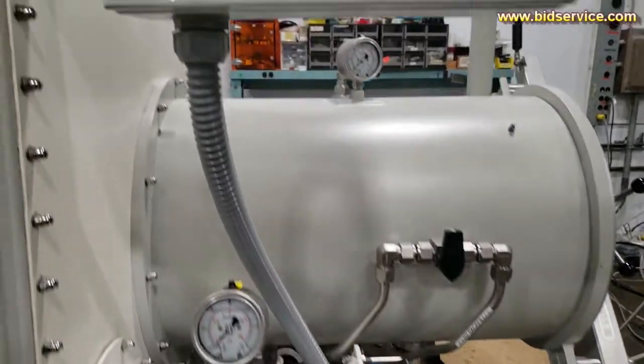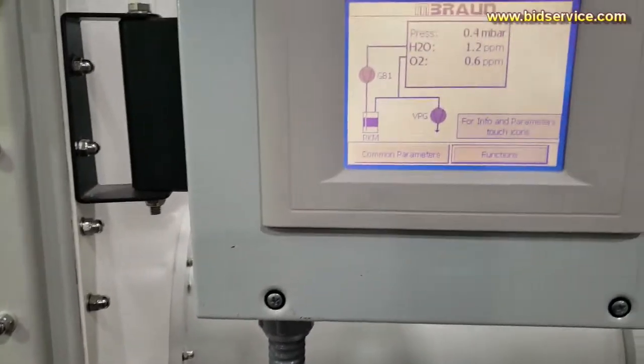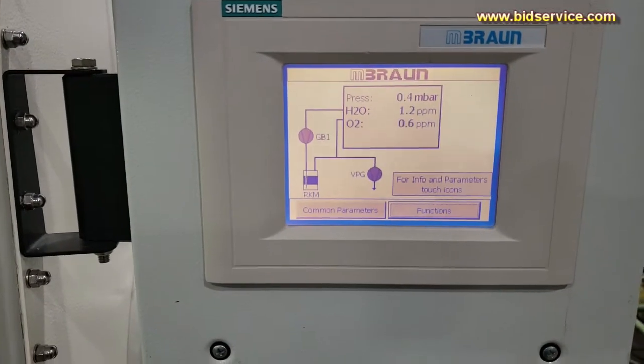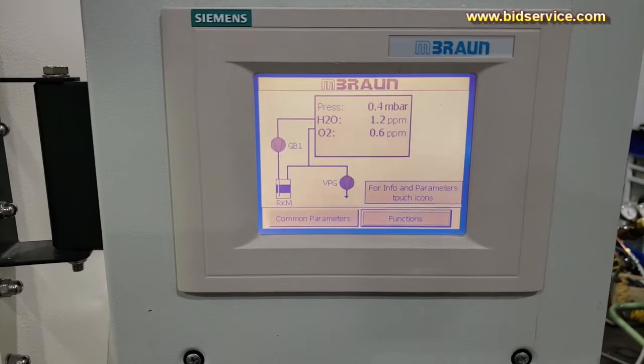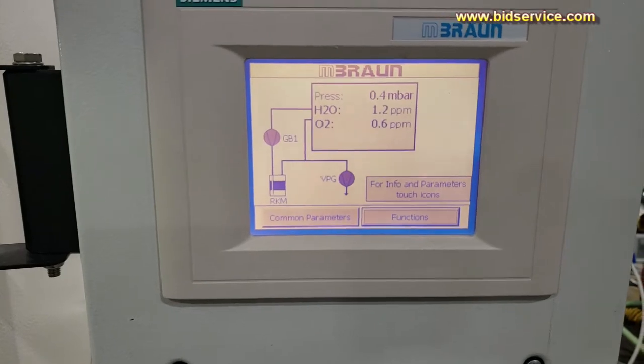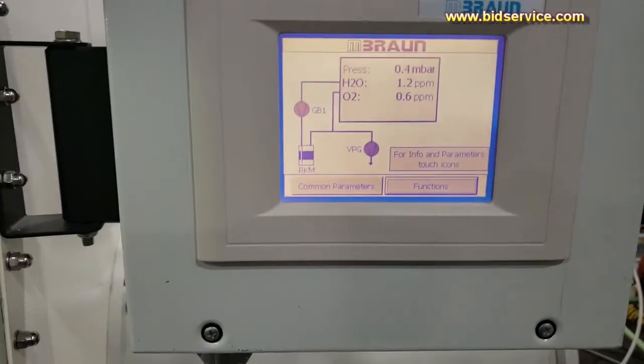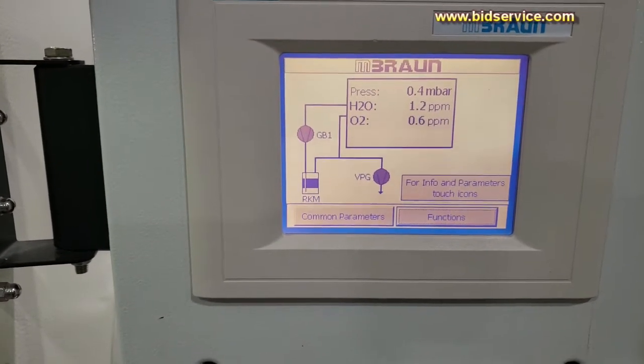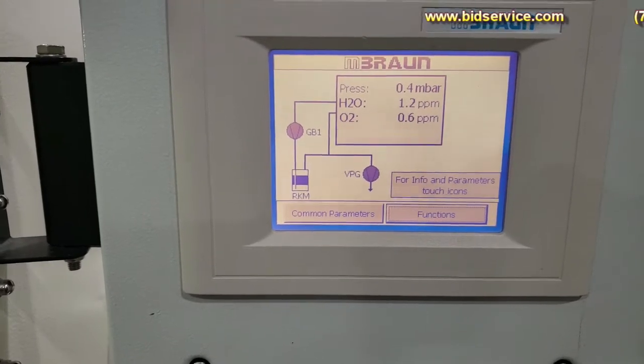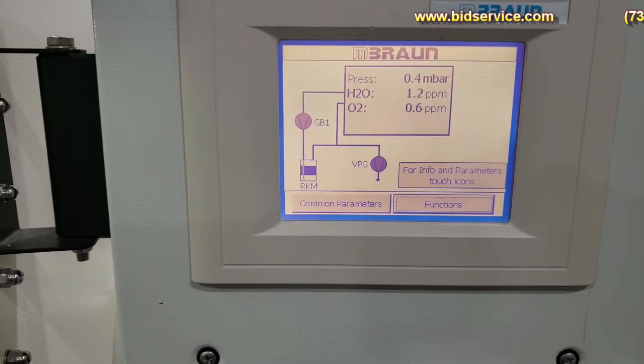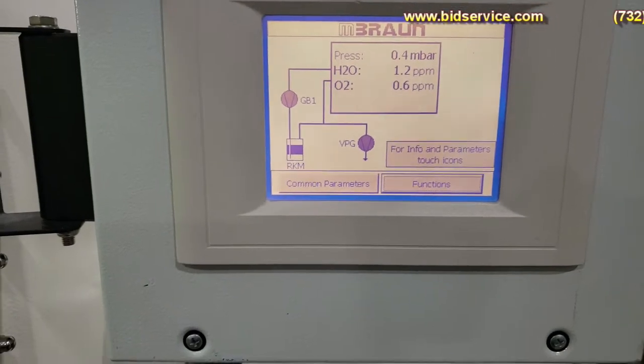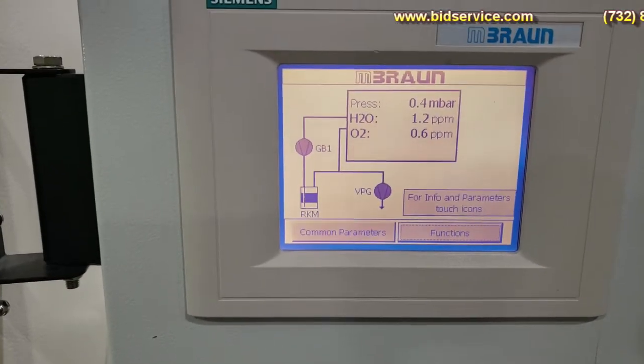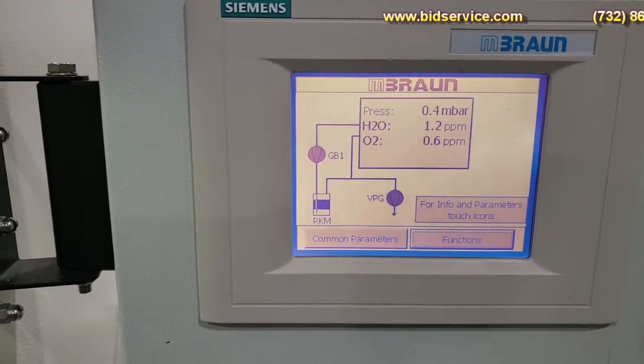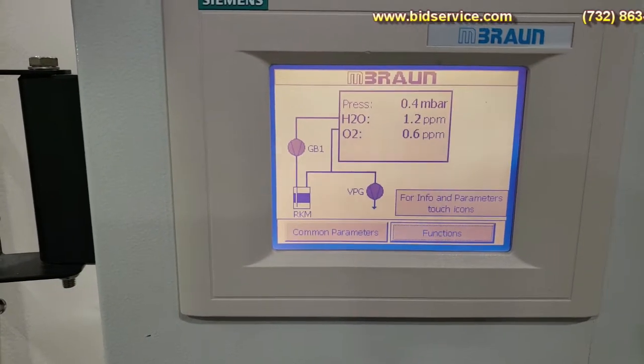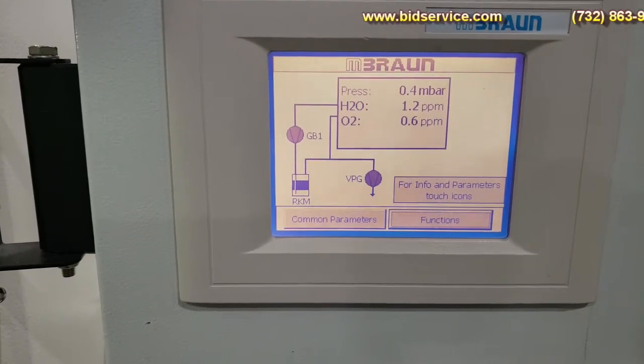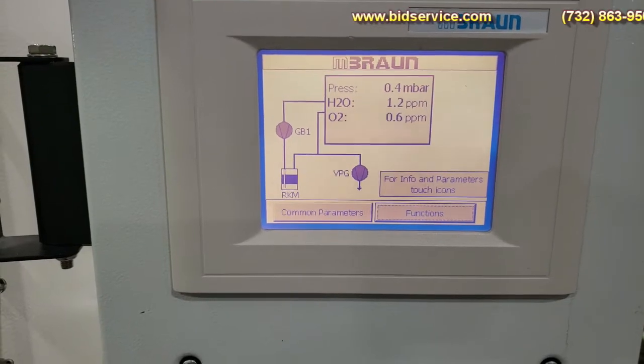But anyway, let's start with your typical power up screen. It will be right here. I have the pressure range set to plus and minus 1 millibar. As you can see, the oxygen is at 0.6 parts per million. Moisture is at 1.2 and dropping. I had the system powered off over the weekend and powered it back up this morning, so it's been slowly dropping from where it was when I turned it back on this morning.